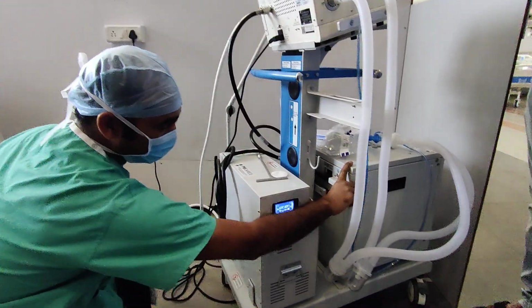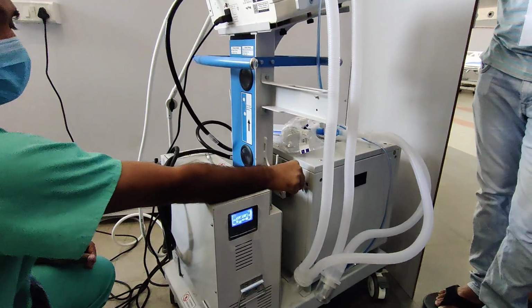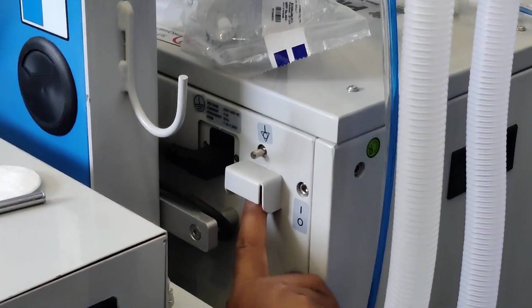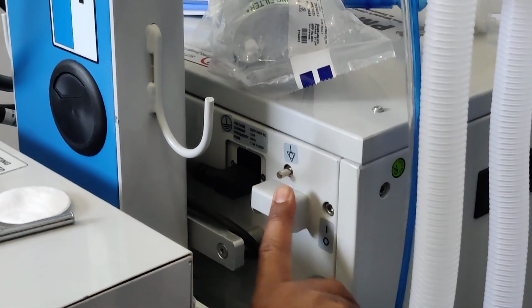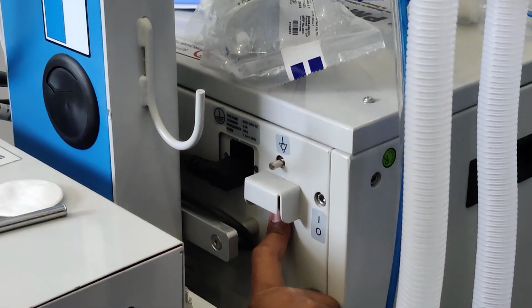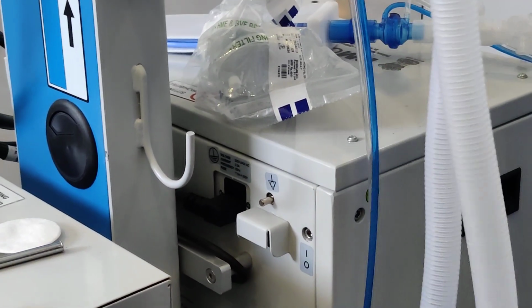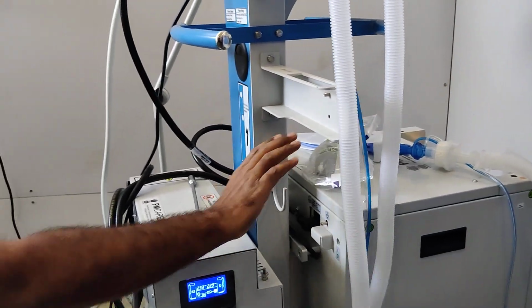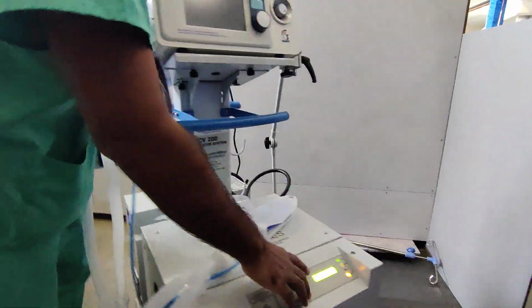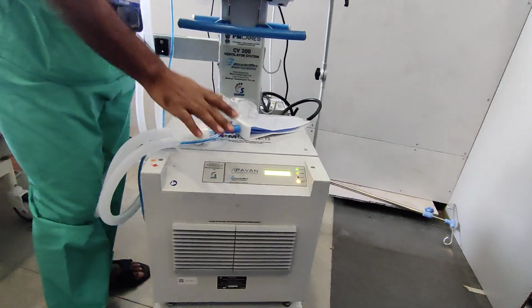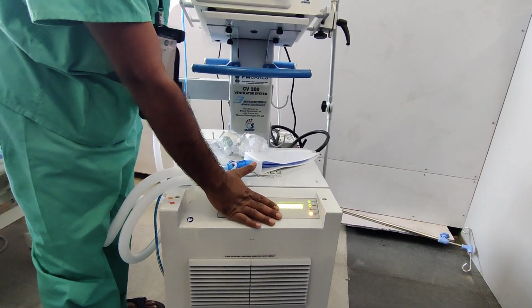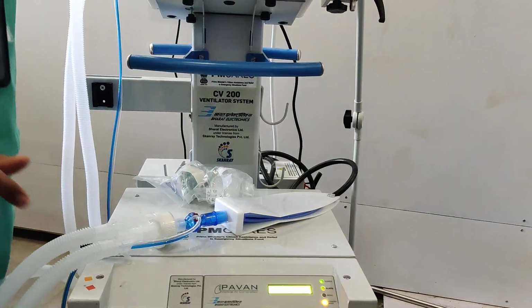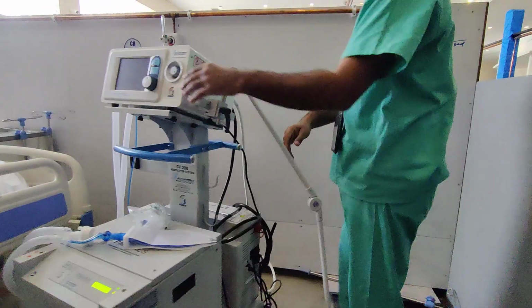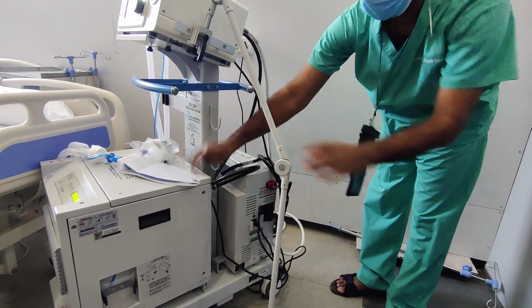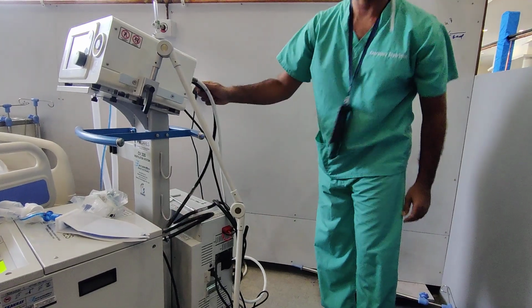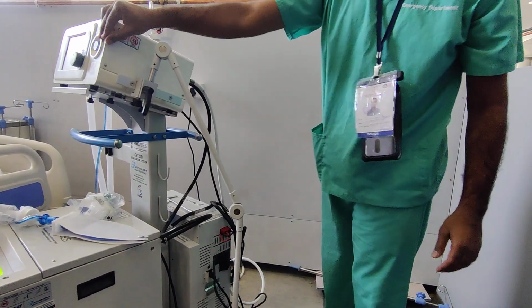Okay, to switch on the compressor, there is a button here below this cap. So you can see, if you just insert your finger in this cover, you will see the one button there. This is switch off. If you go up, it's switch on. So once you switch on this one, you will see one screen here. There are no other buttons on the compressor. So just switch on the button and it will start working on its own. And from the compressor, you can see this output, the air, it blows air from the compressor to the ventilator. Okay, so this is about the compressor.